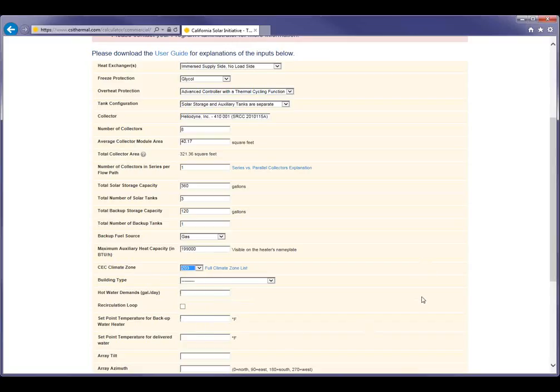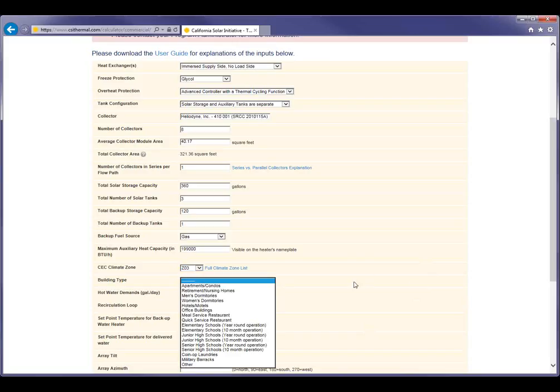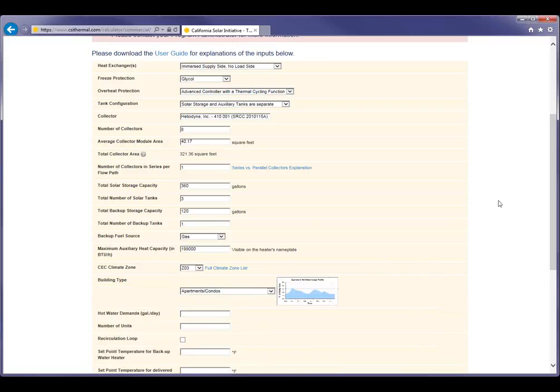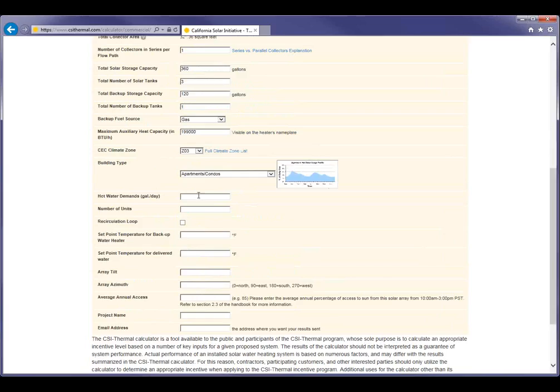I'll go ahead, as with the previous example, and select 3, since I'm in the Bay Area, and that represents the Bay Area. A list of building types, which for multifamily would be apartments, condos, the hot water demand, and if we remember back to my multifamily table of hot water usage, we have 42 gallons per day per unit for up to 20 units. So if we assume a 10-unit apartment building, we would assume 420 gallons per day of usage.